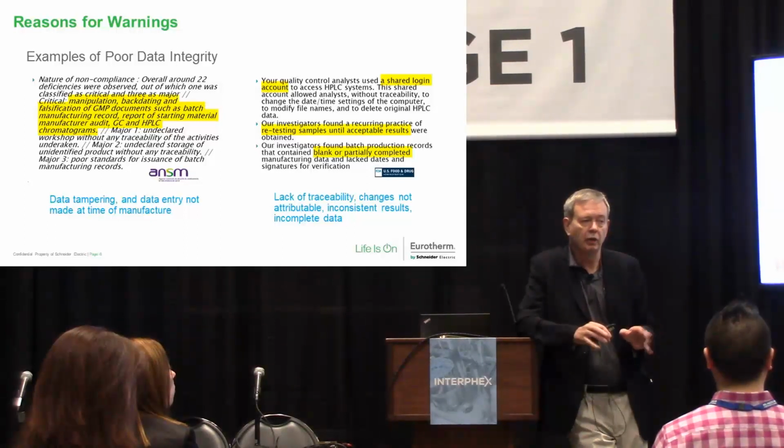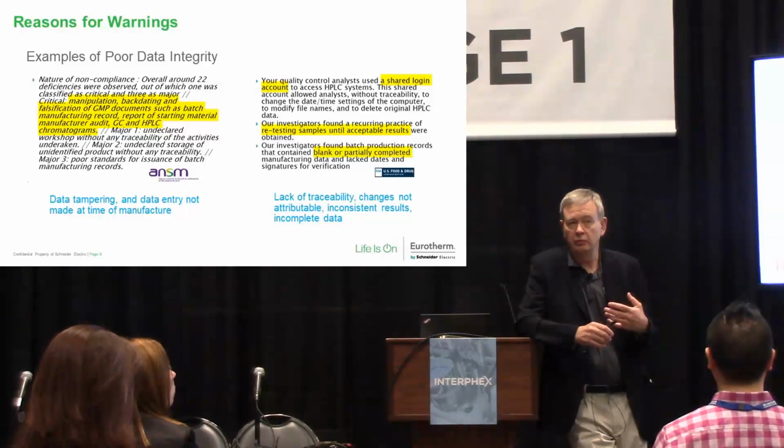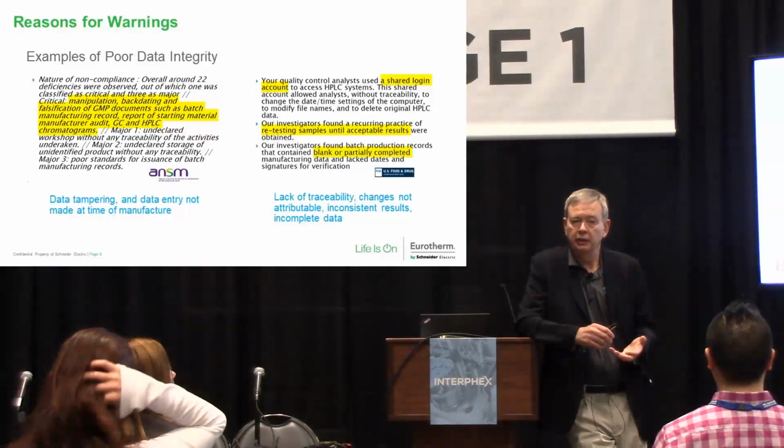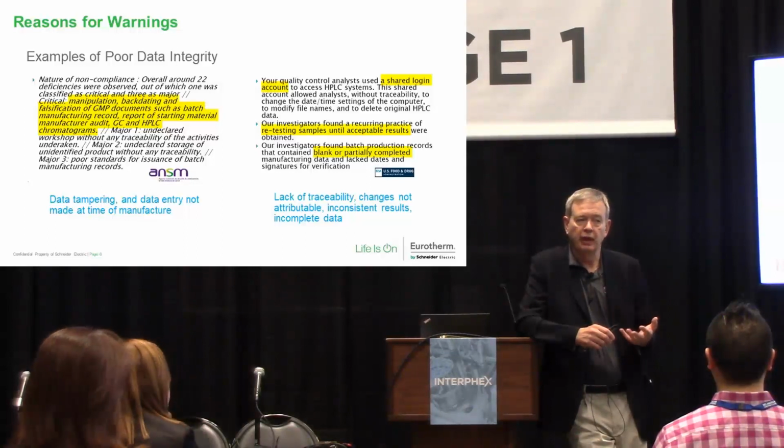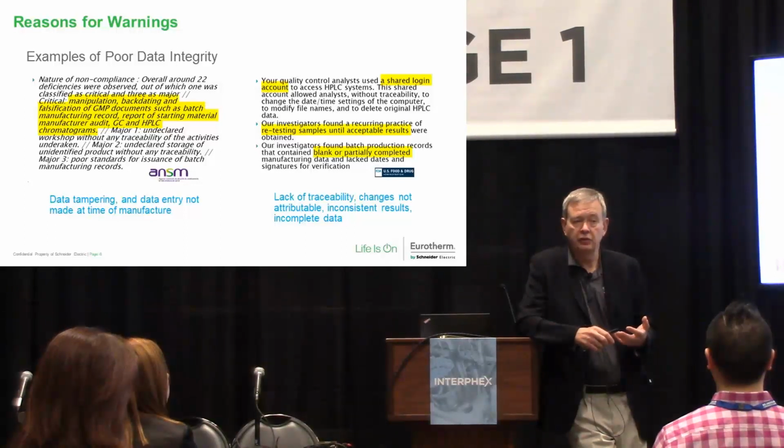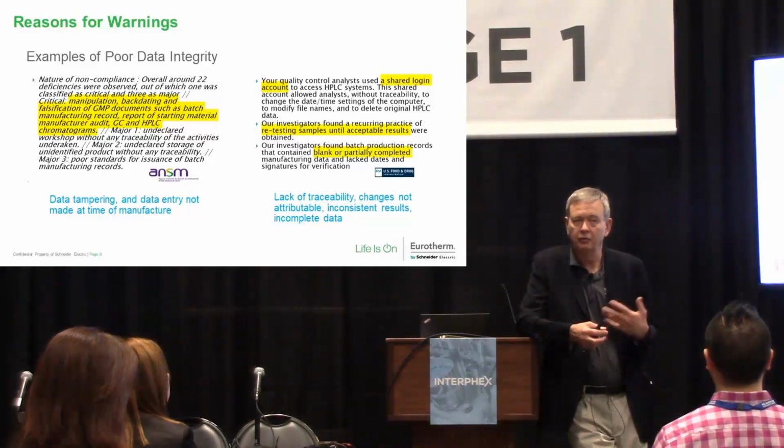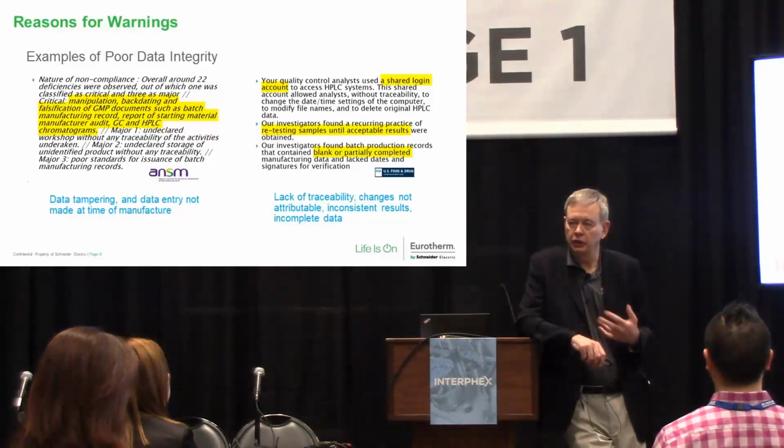That's one of the biggest no-nos in data integrity and guidance, because you have no attributability. If you've got operators and supervisors that are required by 21 CFR Part 11 compliance issues related to electronic signature, if they've got logins that they're sharing, then you never really can look back on that data and have a good feeling and a good understanding for who actually recorded it and maybe when it was actually recorded.